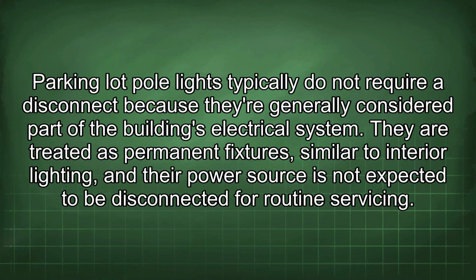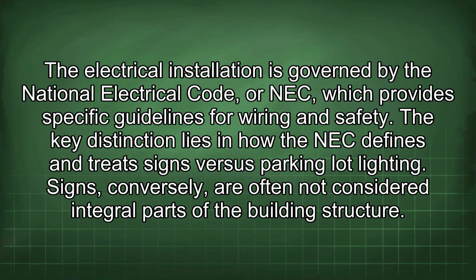Parking lot pole lights typically do not require a disconnect because they are generally considered part of the building's electrical system. They are treated as permanent fixtures similar to interior lighting, and their power source is not expected to be disconnected for routine servicing. The electrical installation is governed by the National Electrical Code, or NEC, which provides specific guidelines for wiring and safety. The key distinction lies in how the NEC defines and treats signs versus parking lot lighting.